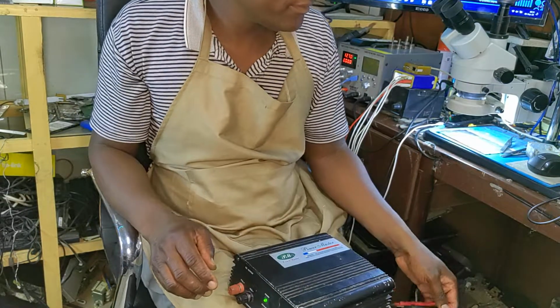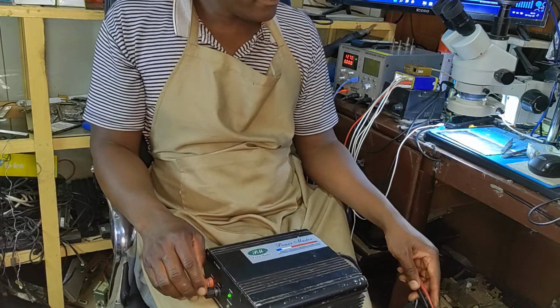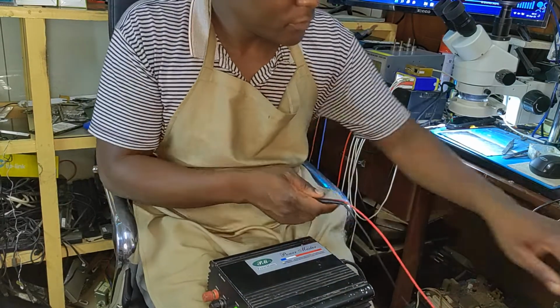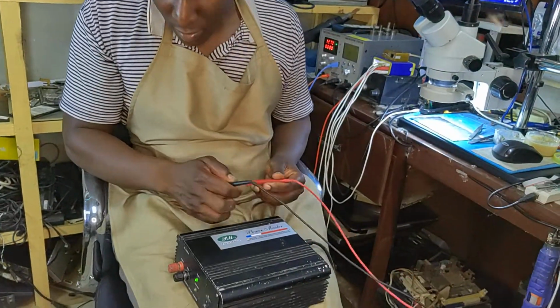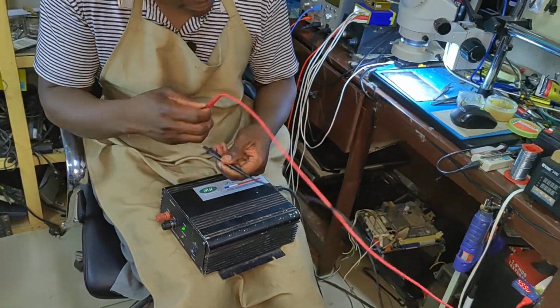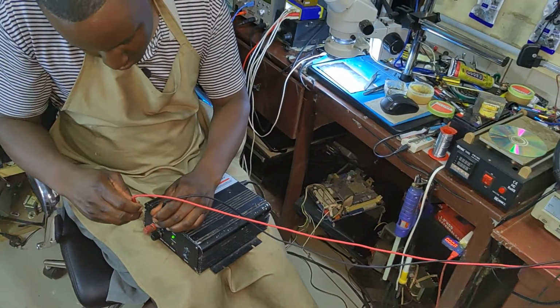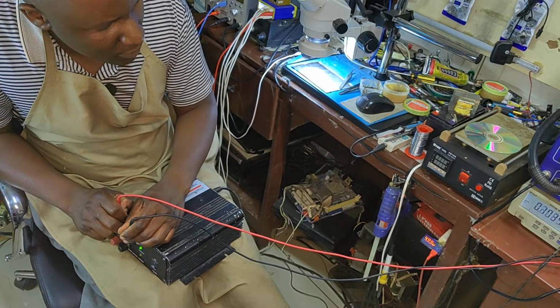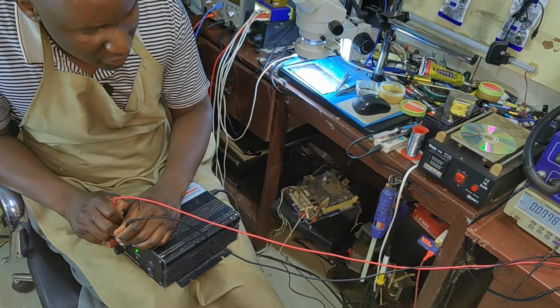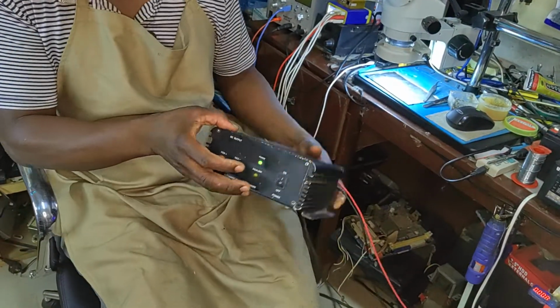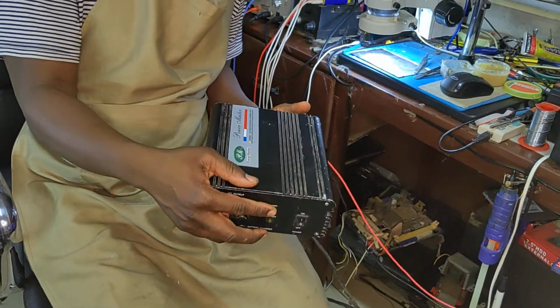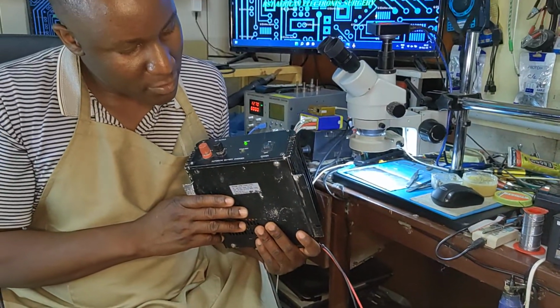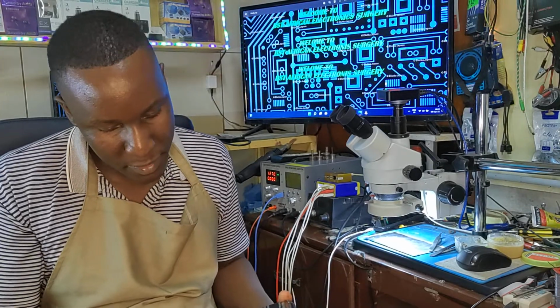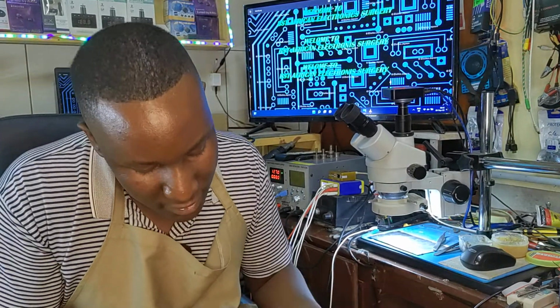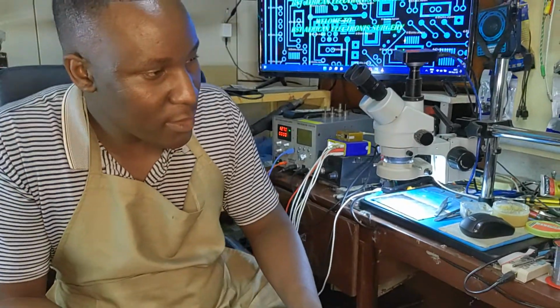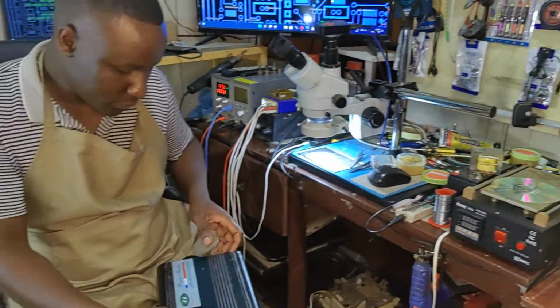Almost 0 voltage, we don't have any power there. Okay, let me test again, to me testing at once is not enough. 0.20, 0.15, almost zero output. But you can see the green light, which indicates that this, I can call it a heavy duty battery charger for some big batteries. We must have output voltage 24 volts and we're getting close to 0.